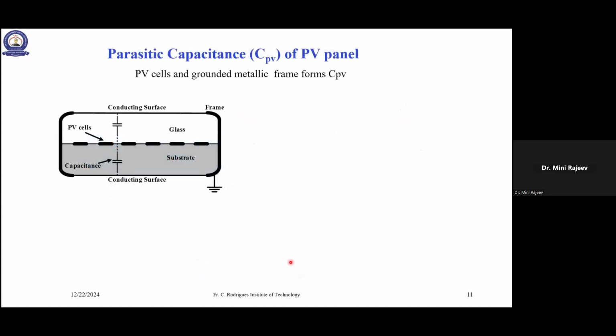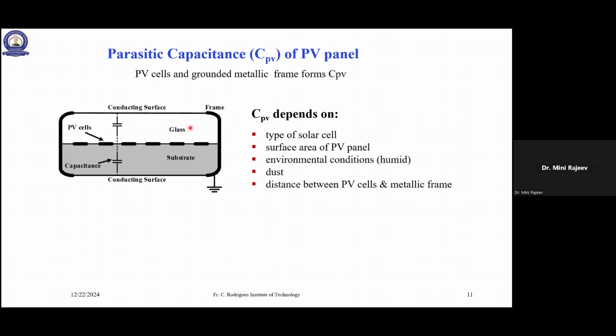So now we will see why this ground leakage current exists in a transformerless inverter. So this is a cross-sectional view of a PV panel. There are PV cells, there is glass, there is a substrate, and there is a metallic frame. And the metallic frame is earthed for safety reasons, so that when an operator touches the PV panel, he should not get a shock. So you have two conducting surfaces and in between some insulating area. So it will act like a parallel plate capacitor. That is what we call parasitic capacitance. There is no physical capacitor, but it will act as a capacitor.